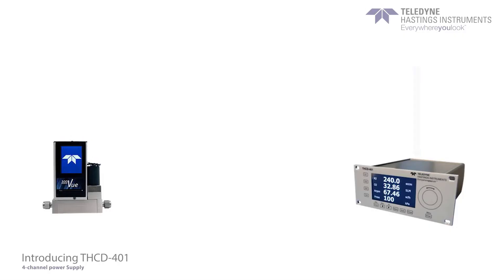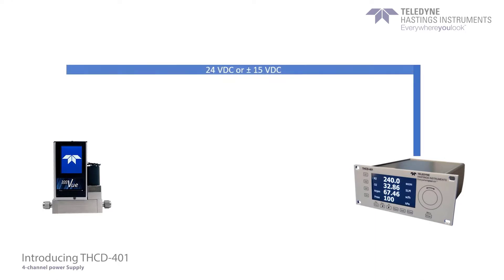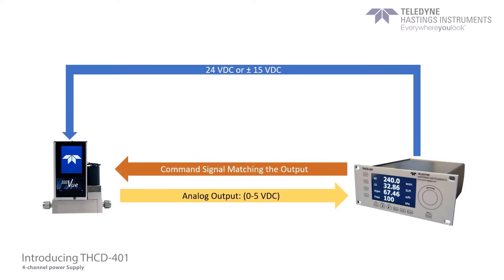How it works is that the THCD-401 sends either 24 volts DC or plus or minus 15 volts DC to power the instruments. Once the devices are turned on, they then send an analog output — for example, 0 to 5 volts — that would be proportional to the full scale range of a flow controller. This is then measured by the 401 to create the readings displayed on the front panel.